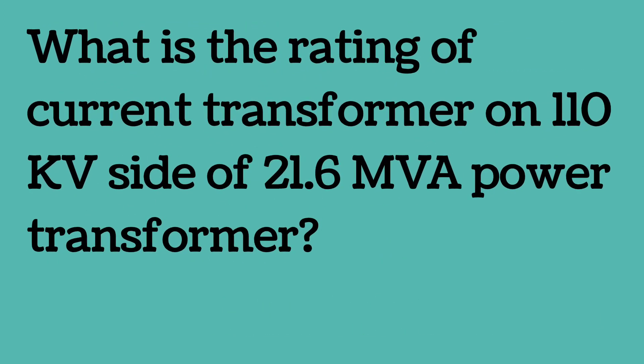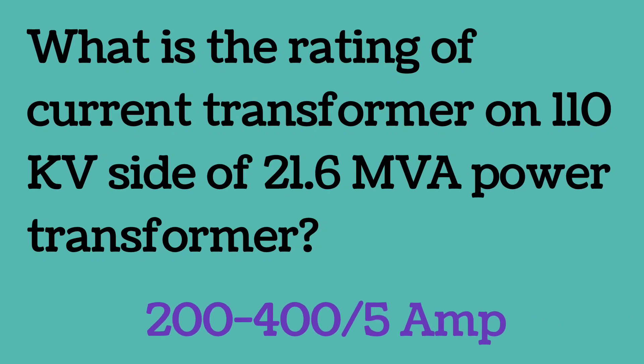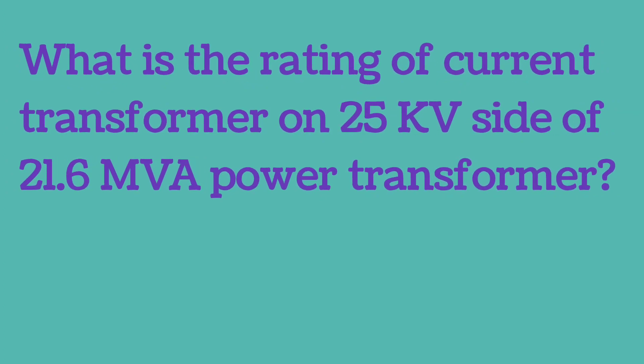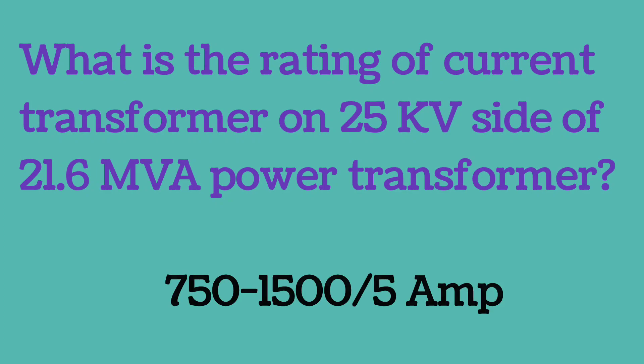The rating of the current transformer on the 110 kV side of a 21.6 MVA power transformer is 200-400/5 amperes. The rating of the current transformer on the 25 kV side of a 21.6 MVA power transformer is 750-1500/5 amp.